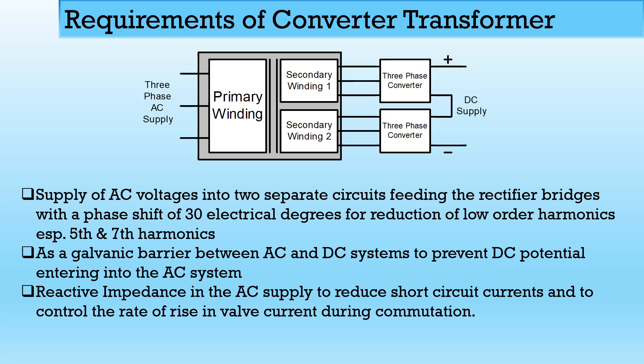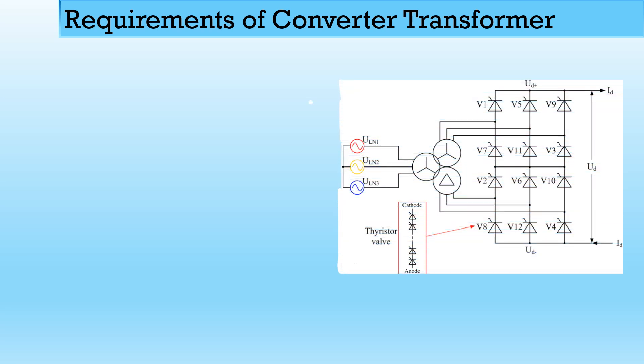Another requirement is reactive power impedance in the AC supply to reduce the short circuit current. As the reactive impedance increases, the short circuit current decreases, and hence the rate of rise of current in the commutation process also decreases. The three-phase voltages are connected to the star of the primary, and the secondary has a star and delta connection. The star connection with the primary star gives 0-degree phase shift, and the delta connection gives 30-degree phase shift.